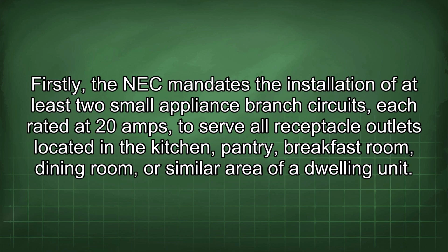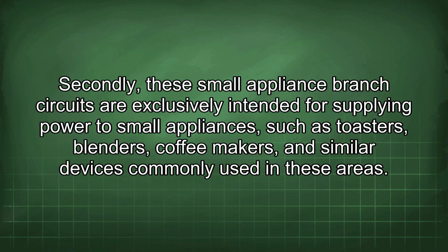Firstly, the NEC mandates the installation of at least 2 small appliance branch circuits, each rated at 20 amps, to serve all receptacle outlets located in the kitchen, pantry, breakfast room, dining room, or similar area of a dwelling unit. Secondly, these small appliance branch circuits are exclusively intended for supplying power to small appliances, such as toasters, blenders, coffee makers, and similar devices commonly used in these areas.